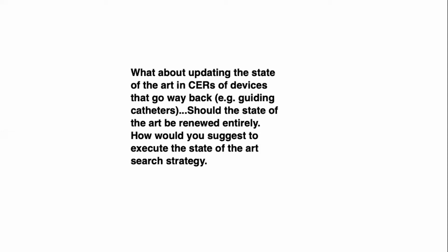Your CER should, whatever the cadence of your CER is, whether it's annual or every 2 years, for example, each time the state of the art should be updated to look for any new professional guidelines or any new information out there that would lend further information or clarity on the state of the art. So for updating the CER for devices that go way back, guiding catheters, yes, we're on that topic, but yes, the state of the art should be updated.